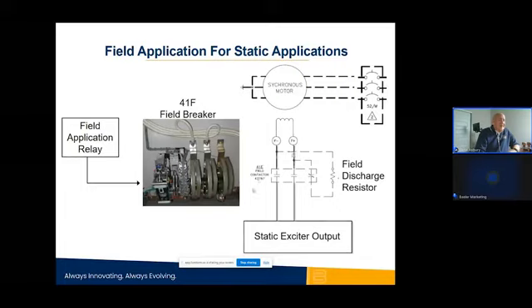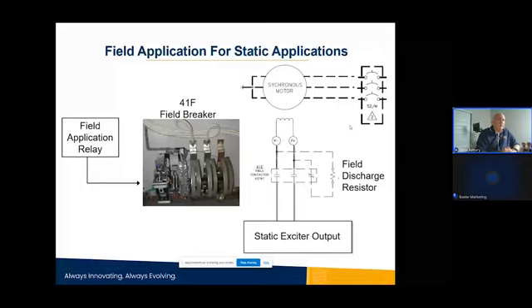So now the static exciter is monitoring the motor's voltage and current to come up with a regulation point, controlling power factor. So we're looking at the real power being absorbed into the synchronous motor and the reactive power being supplied by the synchronous motor. And we come up with a cosine angle between the two, and that's what we're regulating to keep the power factor at a constant power factor.